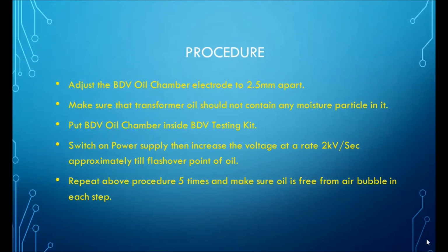If any air bubbles are present in the oil chamber, then what happens? You should know the breakdown strength of oil and the breakdown strength of air. Breakdown strength of oil is more compared to air. If some air bubbles are present in the oil, then the breakdown strength of the oil decreases.